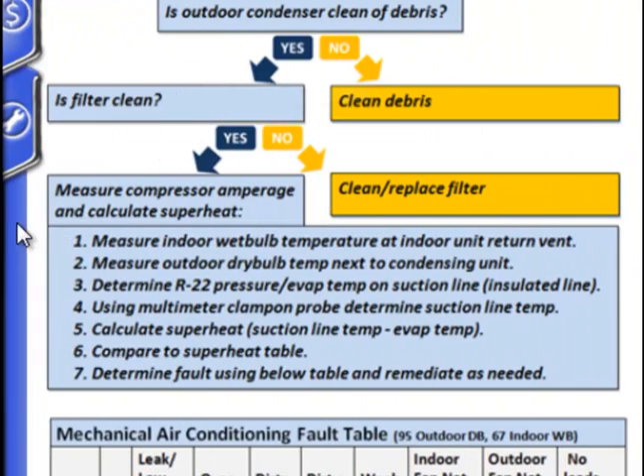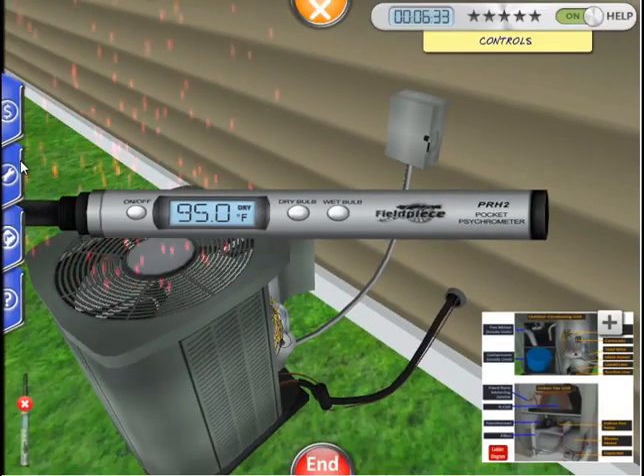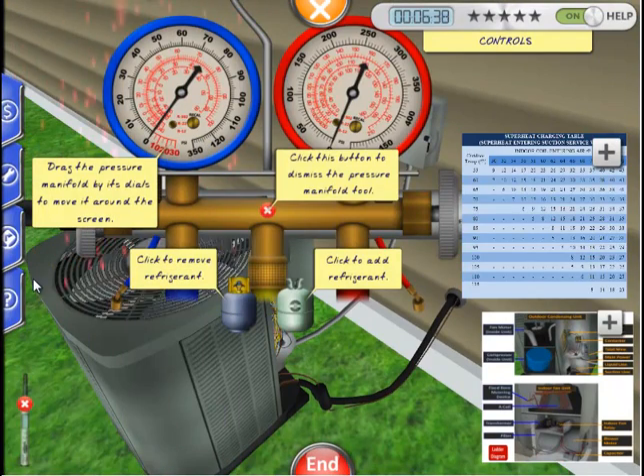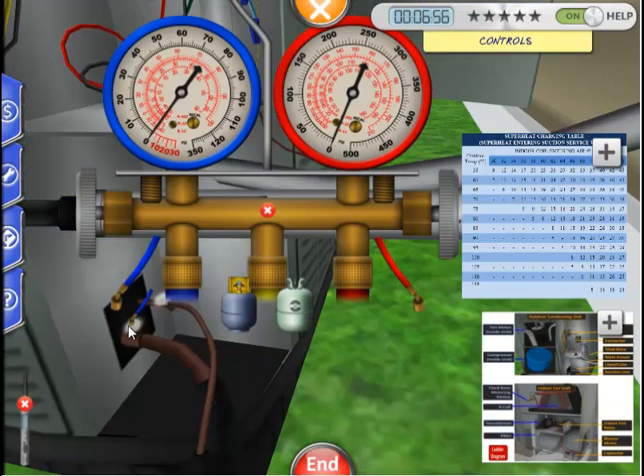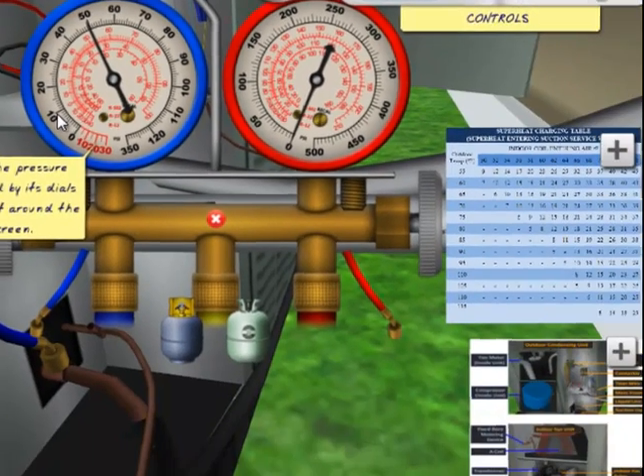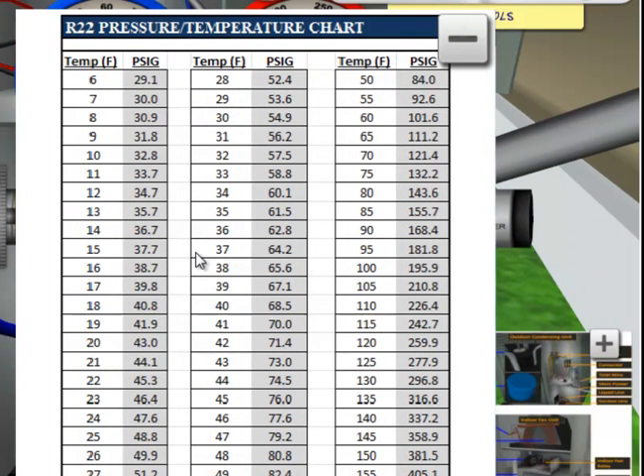Our next step, according to the troubleshooting guide, is to assess the R22 refrigerant pressure and temperature on the suction line. The suction line is the insulated one going into the compressor, and we will use the manifold gauge to determine pressure. Select the low pressure blue gauge and place it on the service port of the suction line. We have a pressure of 50 PSI. We can determine the evaporation temperature by using the provided pressure-temperature chart. According to the chart, a pressure of 50 PSI corresponds to an evaporation temperature of approximately 26 degrees.